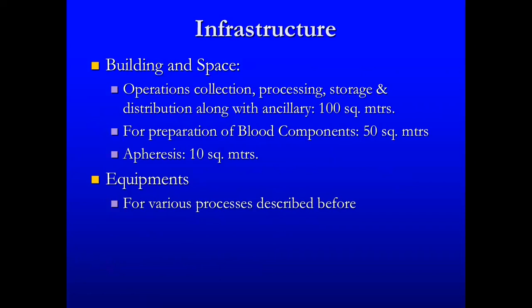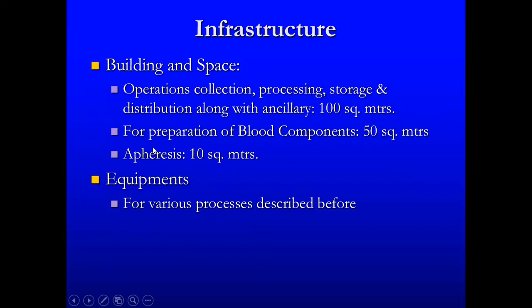There should be adequate infrastructure for the functioning of a blood bank. This includes building, space, and equipment. Rooms should be air-conditioned. For operations including collection, processing, storage, and distribution along with ancillary areas, a requirement of 100 square meters is needed. For component preparation, 50 square meters is required; for apheresis procedures, 10 square meters is required. Various equipment for all described processes is also required.